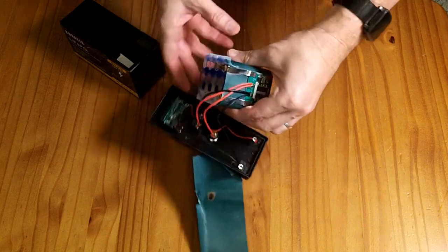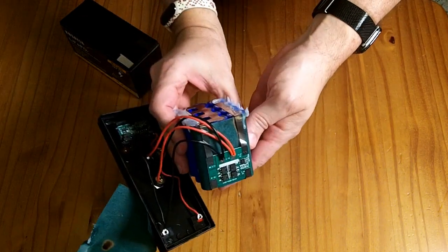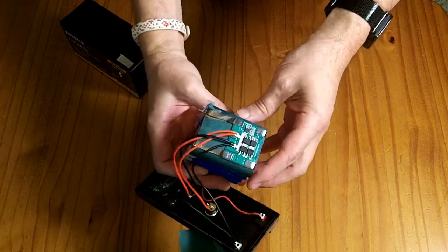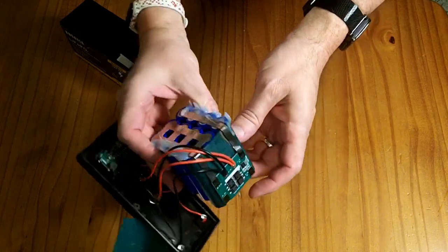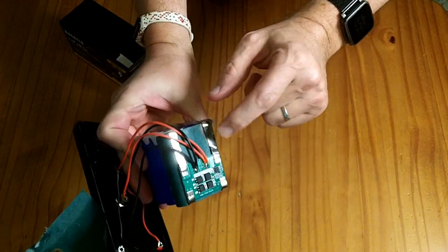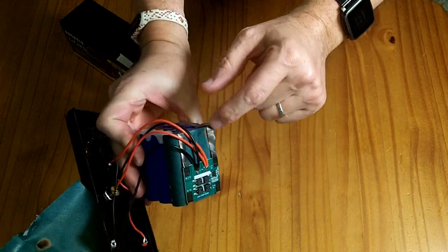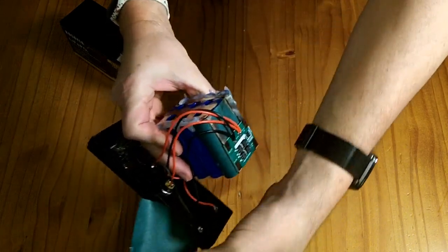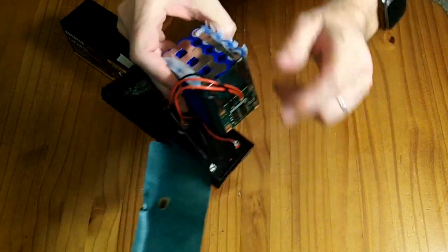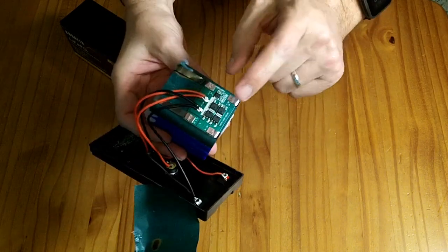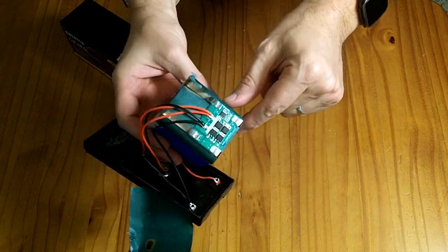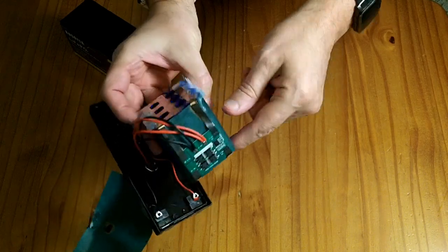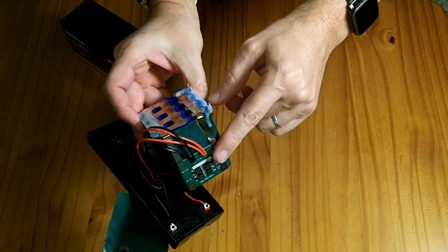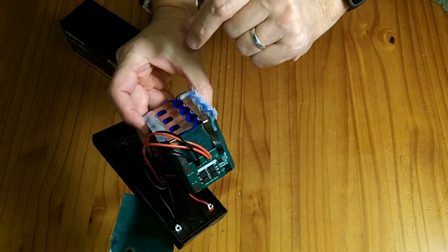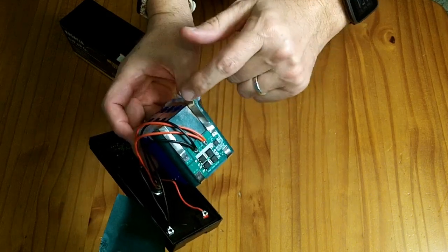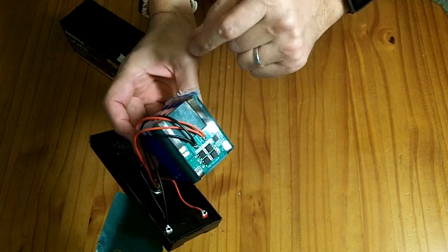The maximum current I tried to draw out of this was 30 amps, and the manual says you can do 30 amps for 5 seconds. But there was clearly a thermal event on this little conductor here, you can see the brown below it and the brown from the paper that was on top of it, and the BMS did not shut down power for that. So I'm not sure if this BMS is correctly sized for the battery pack, or at least correctly sized for this nickel bus bar here.